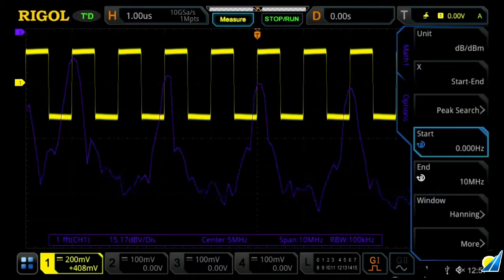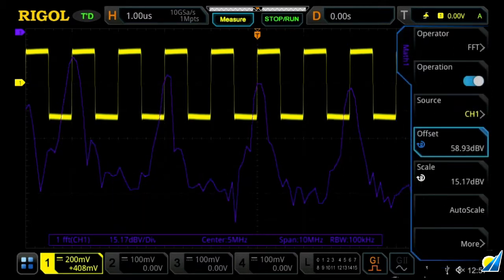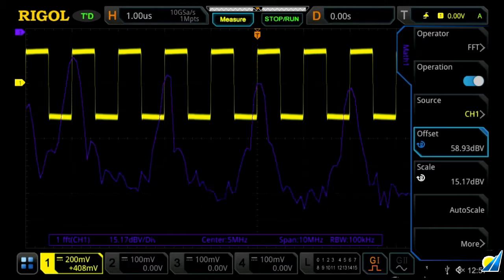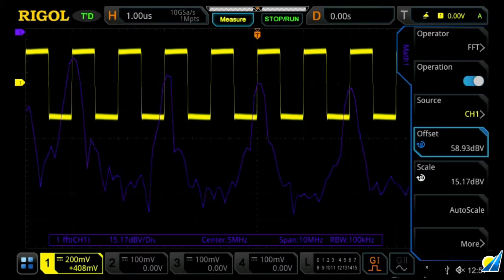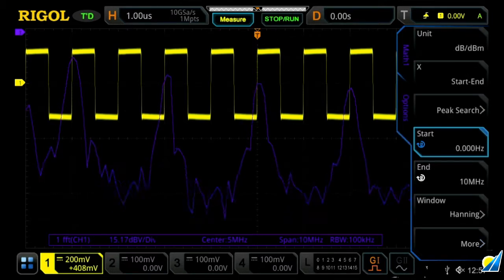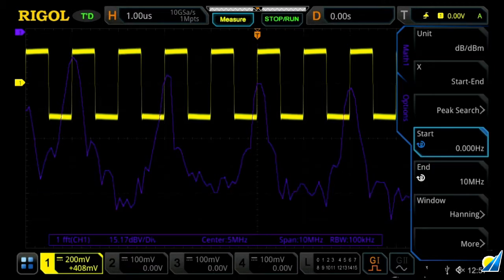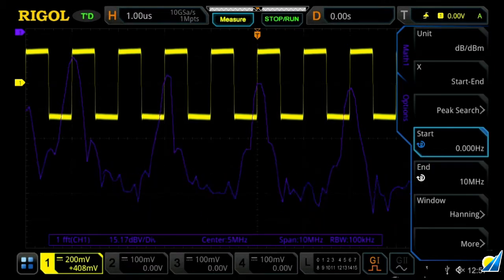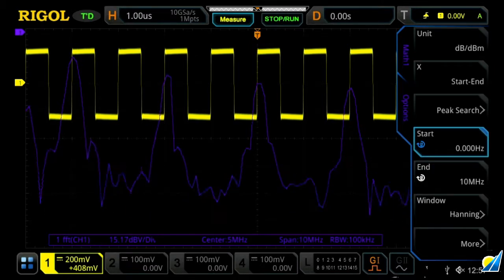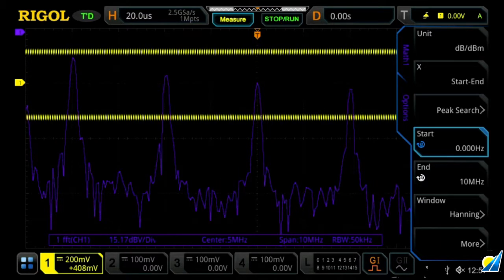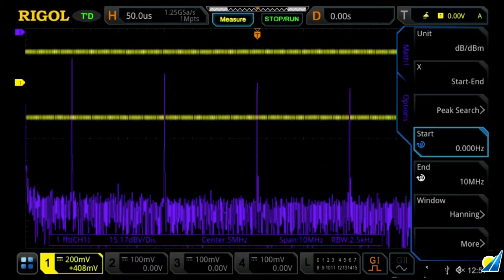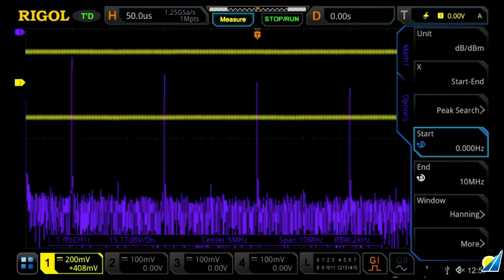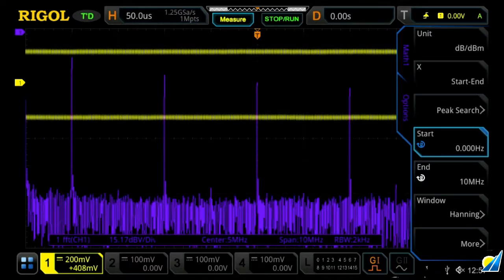Let's turn our menu back on. Within here, we can easily change our offset and scaling if we wish. And if we go into more, we're able to change our scaling as I already showed you. Let's zoom this out a little bit by changing our horizontal display. We're changing our RBW setting down here in the bottom as we scale out a bit.